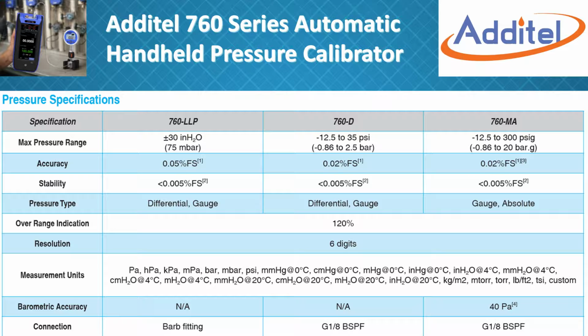Pressure type, one of the things I want to point out about the 760MA is that that unit also has a barometer. It has a barometric module inside, so that if you put gauge modules inside it, or you have a 300 psi gauge module internal to the unit, you can do both gauge and absolute pressures. And that holds if you put other gauge modules internal to the unit as well. If you swap modules out and get 100 psi G, then you could do 100 psi G or 100 psi A, absolute pressure. That's only on the 760MA.